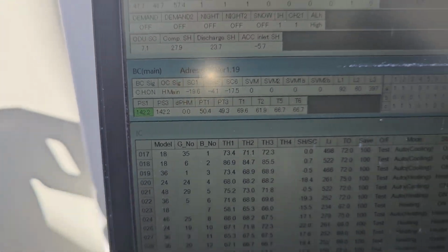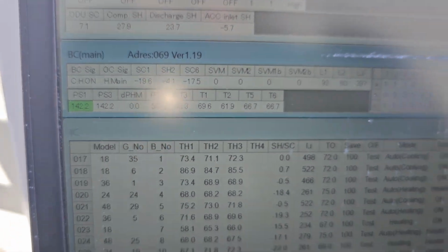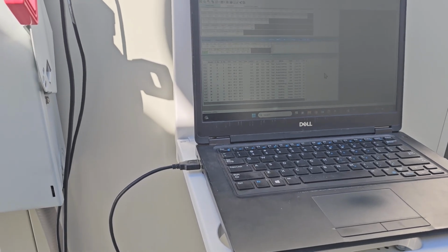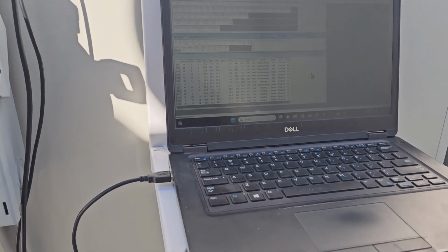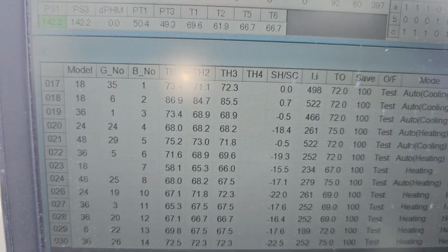So if you look at these thermistors, you got to understand that it says 72, but that might also be just because nothing is happening and it's the same temperature as the room or the air blowing across that coil. It might not be doing literally anything, and it's 72 degrees only because that's what the temperature of the room is.